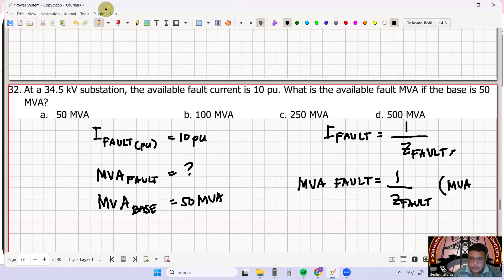Okay. But what is 1 over Z fault? So this is equal to your I fault. So I fault multiplied by your MVA base. And therefore, this is now equal to 10 multiplied by 50 MVA. So therefore, yung ating MVA fault or your short circuit MVA is equal to 500 MVA. So therefore, this is letter D.